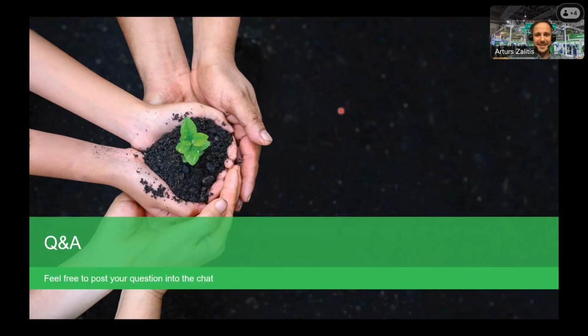No, I believe the session was very clear, and I believe that Martin really highlighted the main value that we have around this new Easy three-phase modular UPS. This UPS is really flexible in terms of evolutivity, if we want to increase the power, scalability, but also, and a very important point that Martin highlighted, the safety. It is flexible but really safe due to this live swap design.